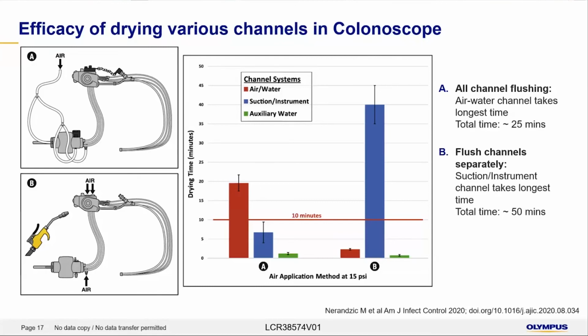One thing to mention is that this study didn't compare the air pump or the forced air drying individually. They didn't compare it to a channel purge storage cabinet. And you might ask the question, okay, this is people doing research and science, does this really translate into the clinical world? Well, Saliu in 2016 actually compared the contamination rate of patient-used scopes, and what they found was that when they used a channel purge storage cabinet, only 9% of their scopes had high concern organisms. If they used a regular storage cabinet with no forced air going through the channels, 32% of their scopes were contaminated with high concern organisms. So it does translate to real life, and it does mean that if you don't have adequate drying, you will have microbial replication and you will get yourself in trouble, potentially with biofilm formation because of that.